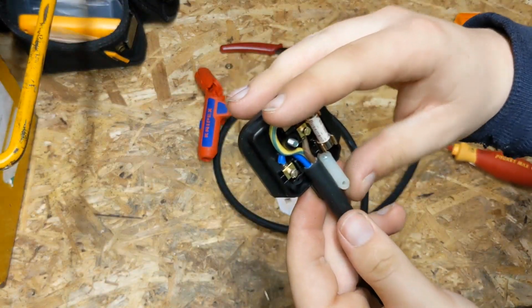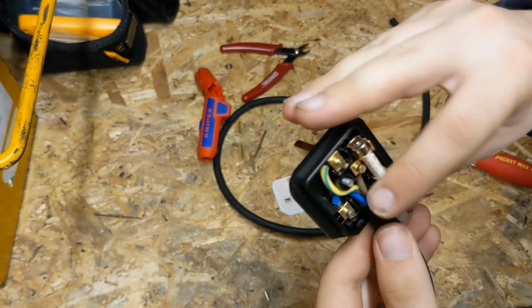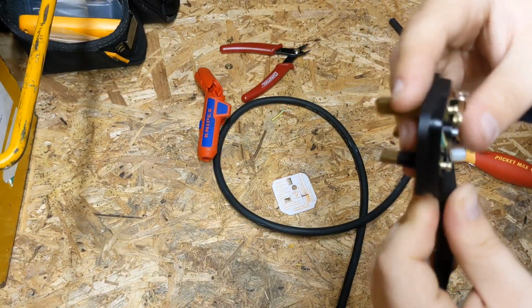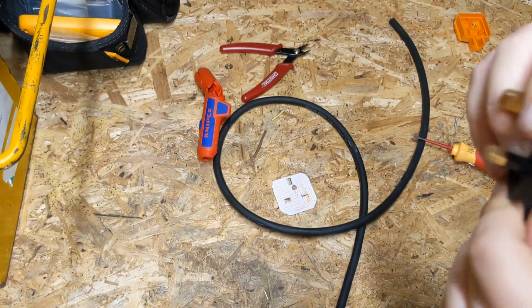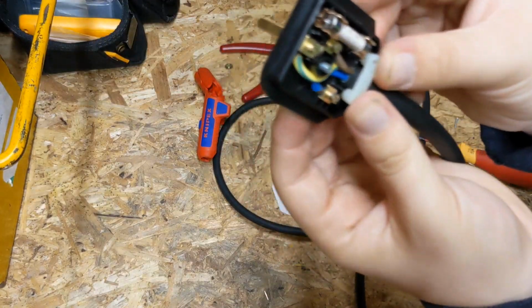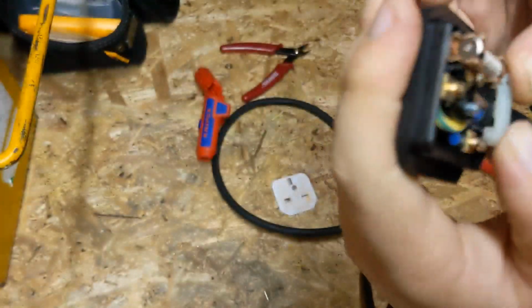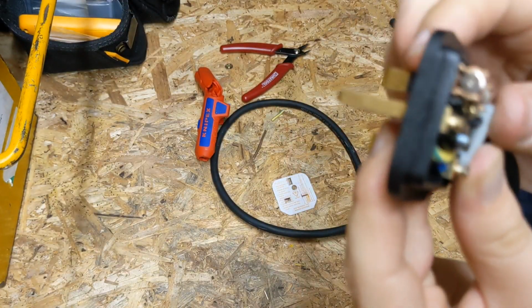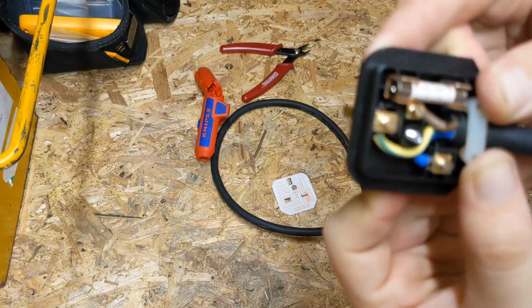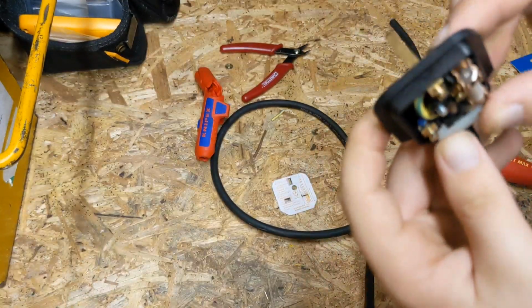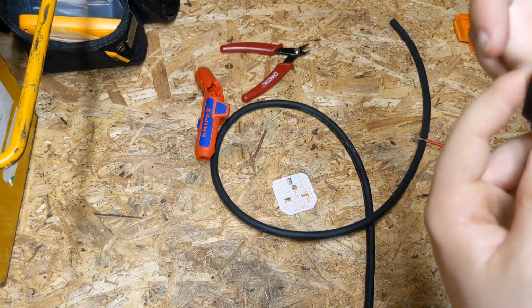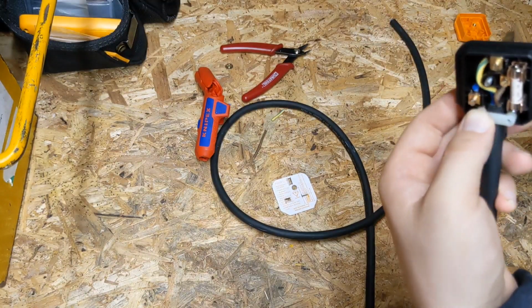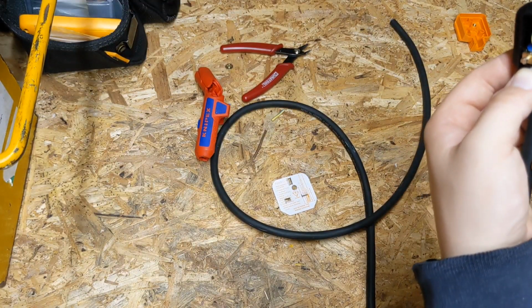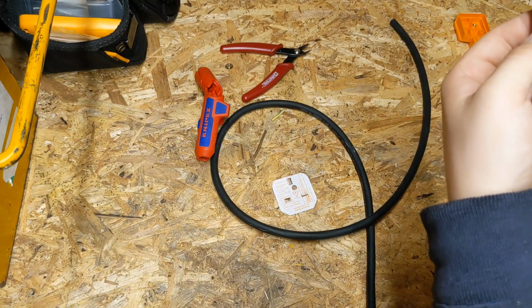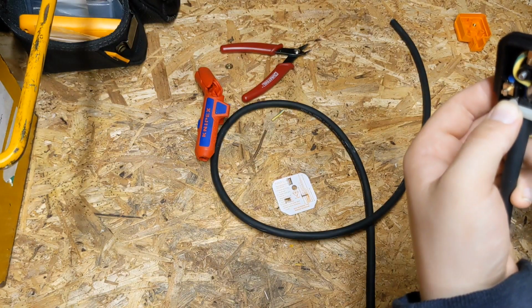The reason why we turn that cable grip piece around is because if you had it on the other side, you'd really struggle to get it over the rubber cable. Rubber cable's got a really thick, tough sheath on it, and if you had it on the other side, you'd really struggle to clamp that down. So if you turn it around, you get a bigger hole, it clamps better, and you don't end up bending and breaking the cord grip.